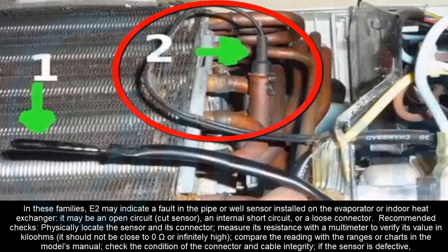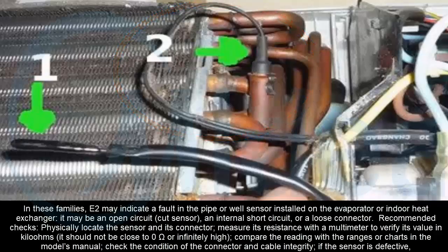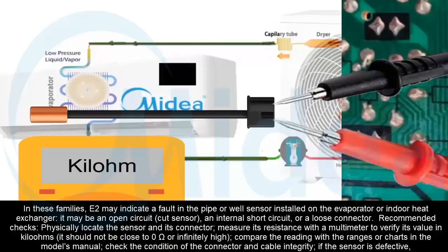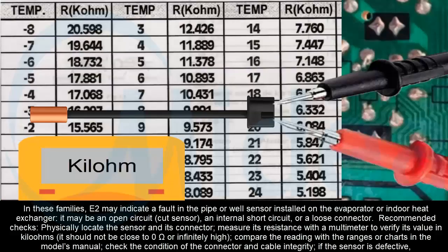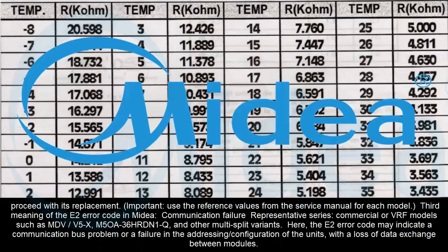Recommended checks: physically locate the sensor and its connector, and measure its resistance with a multimeter to verify its value in kiloohms. It should not be close to 0 ohms or infinitely high. Compare the reading with the ranges or charts in the model's manual. Check the condition of the connector and cable integrity. If the sensor is defective, proceed with its replacement. Important: use the reference values from the service manual for each model.